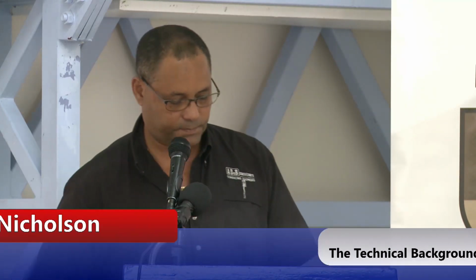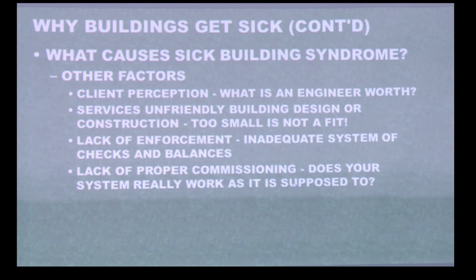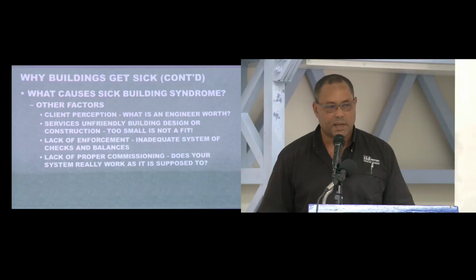Lack of proper commissioning. I've been called into jobs where there's a problem, where I haven't installed it, or designed it, should I say, I don't install. And it was never going to work in the first place. Somebody put it in, yeah, that looks good, sealed it up. It wasn't going to work. Either too big, too small, the air wasn't getting back. It just didn't work. And people struggle on with that and then complain that they have a problem with their building being sick. Well, it started off wrong in the first place. It was never going to get right by servicing or changing this or changing that.